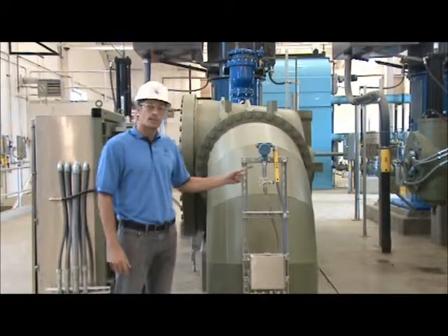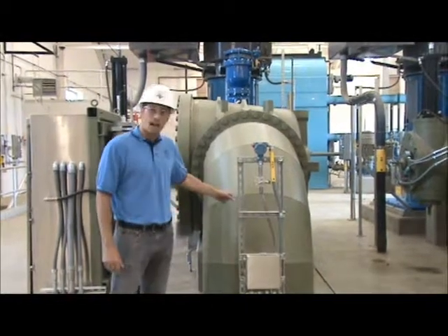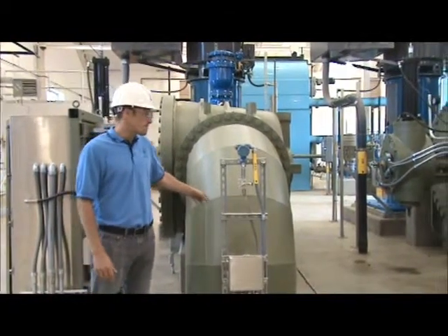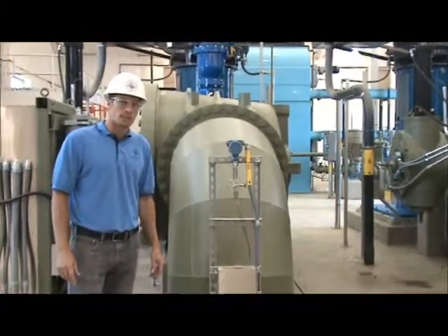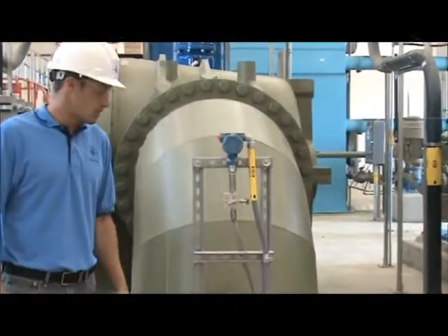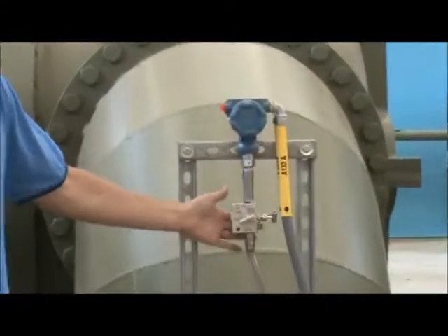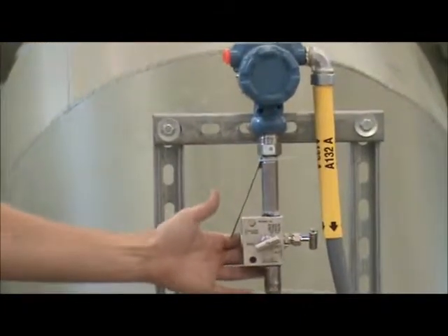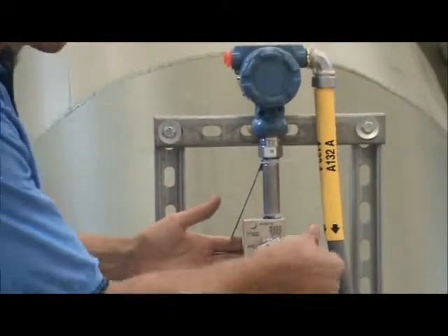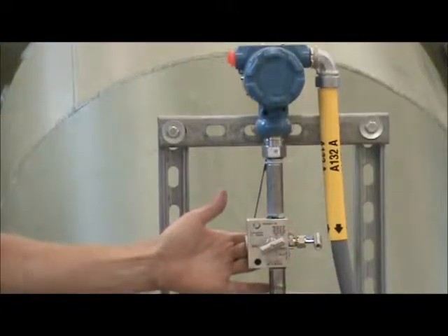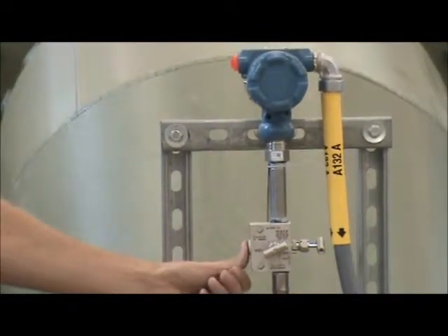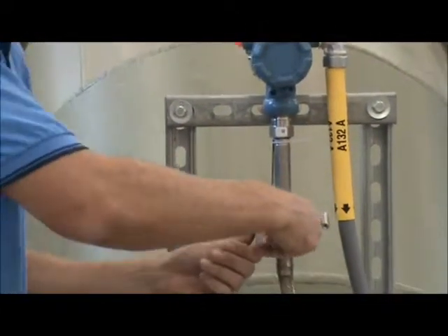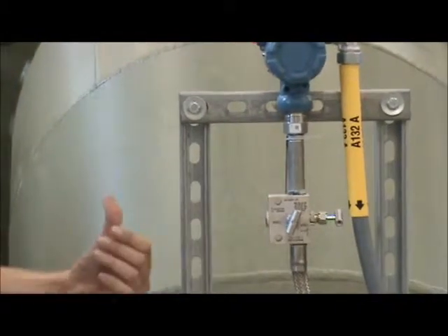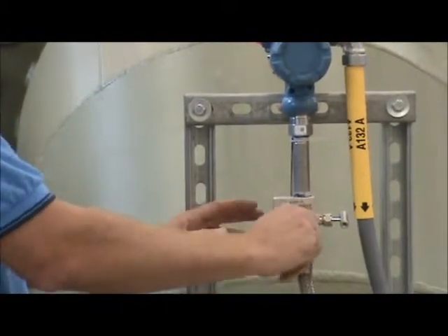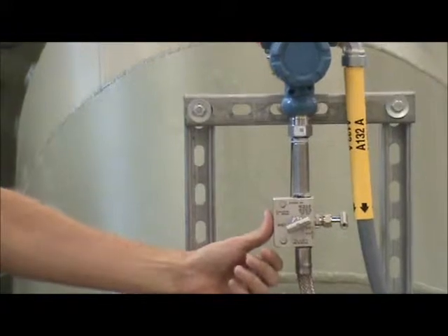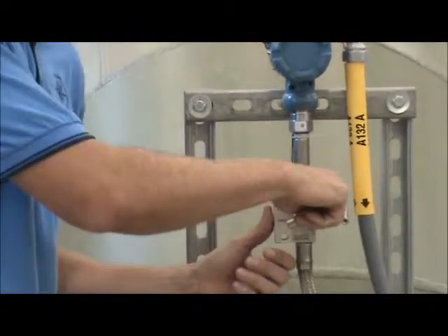This is the pressure transducer on the downstream side of the pump system. It sends a 4 to 20 analog signal back to our controller. And then there's also a purge valve in the sensing line. With this one, you open up the flow into the transducer. You remove this plug, and then you open up this switch in front to have the air purge. And you close it, return the plug in, but you leave the sensing line open.